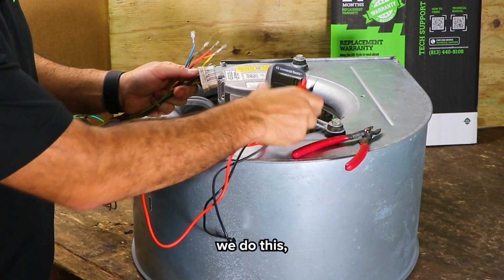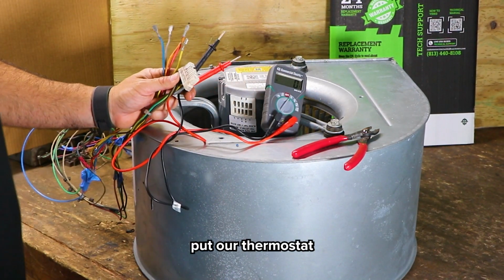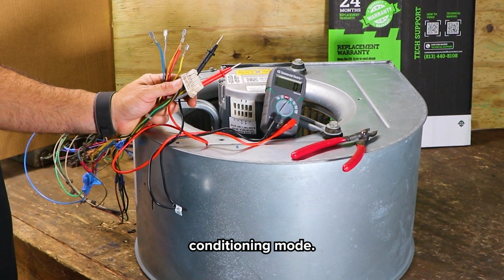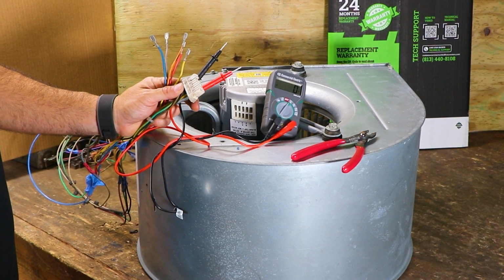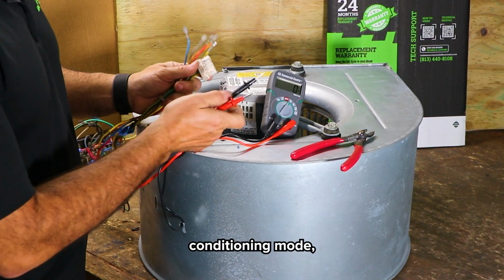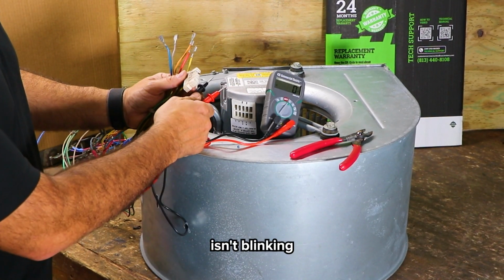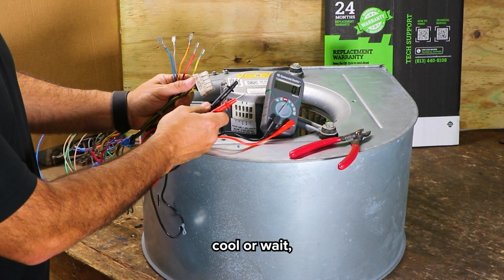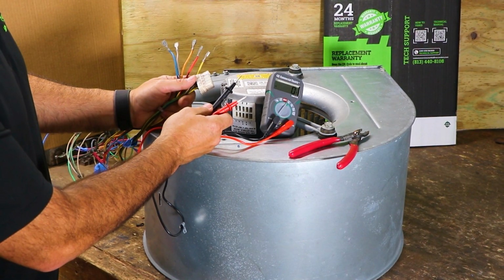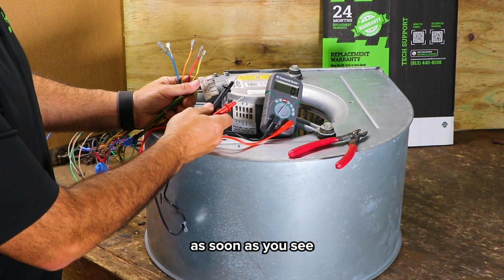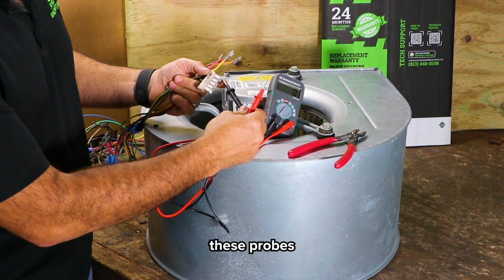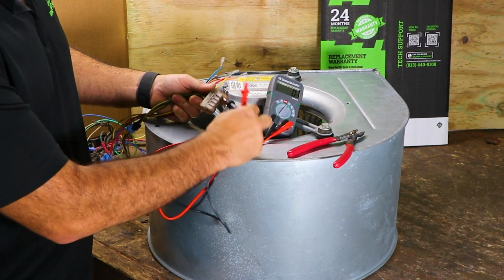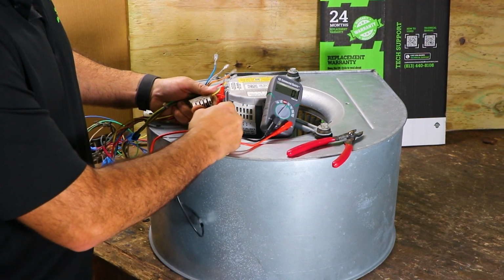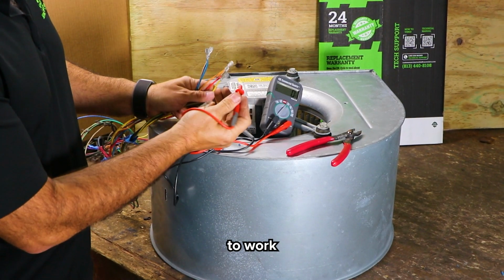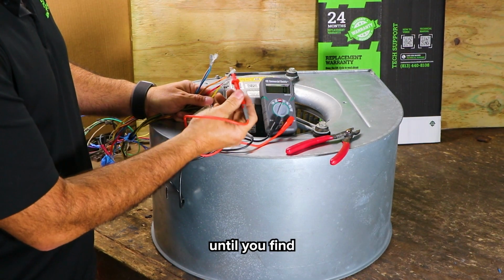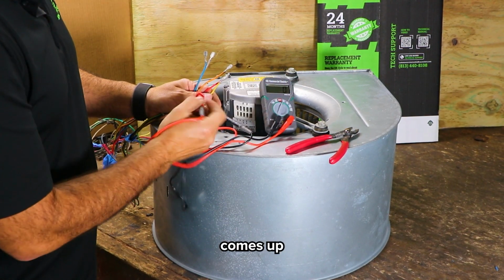We take our thermostat and put it in air conditioning mode. Once it's in air conditioning mode, make sure your thermostat isn't blinking cool or wait, that it's solid. As soon as you see that it's solid, put one of these probes in the C, then work through these until you find the one that comes up to voltage.